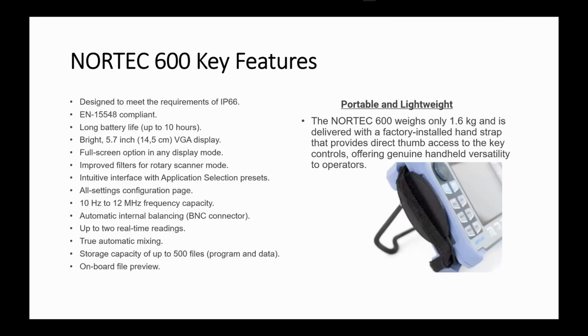Some key features about the Nortec 600: it's designed to meet the requirements of IP66 like most of our other instruments, and it's EN 15548 compliant for those of you overseas in Europe. It has long battery life, up to 10 hours on one charge, full screen option in any display mode, and a bunch of improved filters for rotary scanner mode. It has automatic internal balancing, up to 2 real-time readings, and storage capacity of up to 500 different files, both programs and data included. It also has onboard file review. It only weighs 1.6 kilograms and is delivered with a factory installed hand strap, so you can carry it with one hand and use one-handed control.